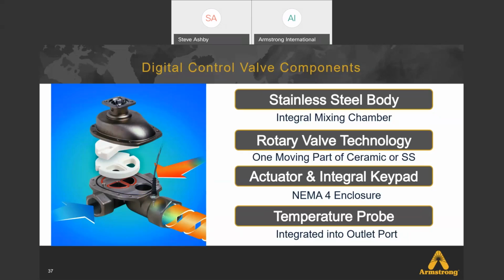Again, with the rotary design, there's not a lot of maintenance involved. Some seals are in there, but again, there's not a lot of compression. There's not a lot of vertical moving of a stem like on a linear valve that can really cause some issues with packings and leaking and a lot of maintenance. This valve just doesn't need a lot of attention.